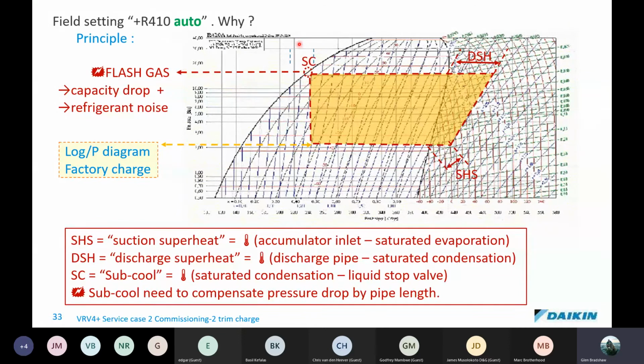Now if we only open the valves on the system and didn't add any refrigerant, the system would run undercharged, and this would bring the subcooling into a position where there would be flash gas. So we need to bring the subcooling through to where it is liquid. If we have flash gas, we have a capacity drop, and we have additional refrigerant noise because we've got bubbles traveling through the piping.